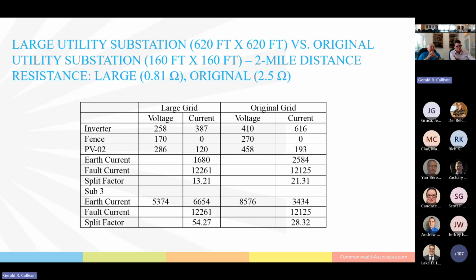Okay, so what we have shown is that by changing the distance between the utility and the collector station, the voltages at the collector station and at the solar plant change dramatically. So what happens if we go back to the original, with 2 miles between them, and we take the utility substation and instead of making it 160 foot by 160 foot, we change it to 620 feet by 620 feet. Well, as Gerry said earlier, the footprint of the ground grid has an impact on the resistance value. And as you can see, the resistance for the large utility grid is now 0.81 ohms as compared to the 2.5 ohms of the original.